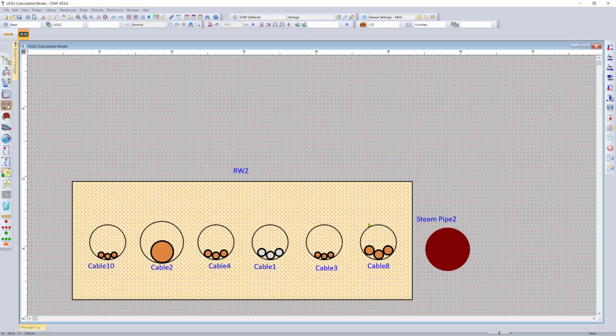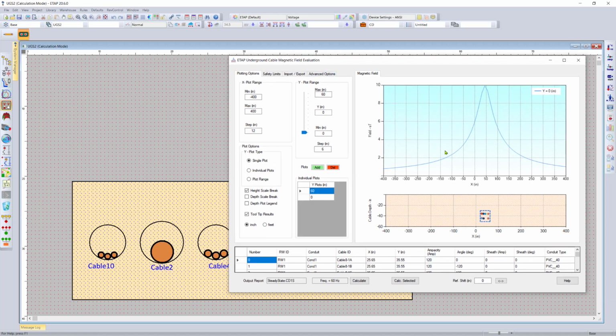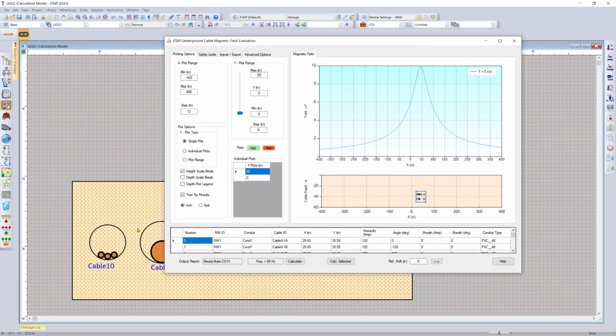From our underground raceway system program, we can bring up the magnetic field calculator and essentially look at the magnetic field strength that's being calculated for all the conductors in this raceway. The calculation, as I mentioned earlier, is based on ampacity as well as the current angle, which makes a tremendous difference between the magnetic field strength at normal balance condition versus unbalanced condition. So it's very important to get these current values as well as the angles correctly and preferably directly from the one-line diagram. And that's exactly what you can do in ETAP.